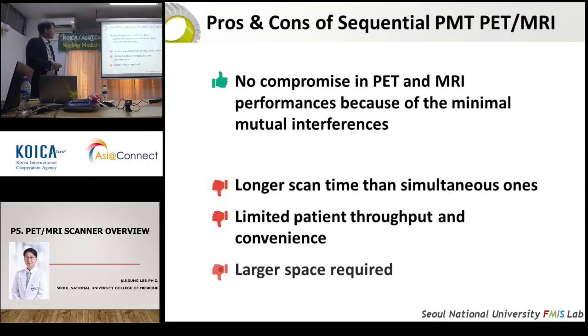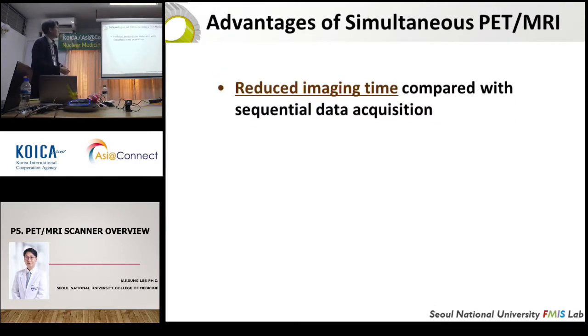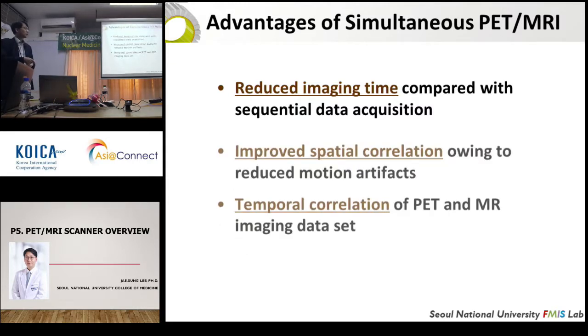But the sequential PET MRI system has some pros and cons. We can say that there is no compromise in the PET and MRI performance, because there is minimal mutual interference since we use separate machines. But I think there are more cons. It requires much longer scan time than simultaneous systems, and that causes limited patient throughput and convenience. And we need very large space for both the PET and MRI scanners. That is why they have not been quite successful in terms of marketing of this kind of PET MRI scanner.